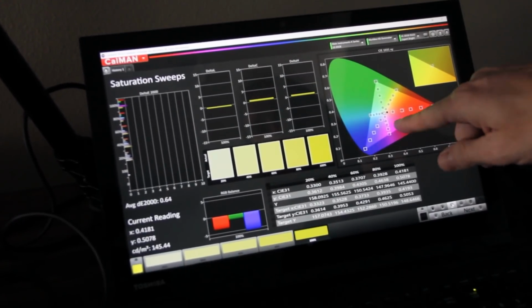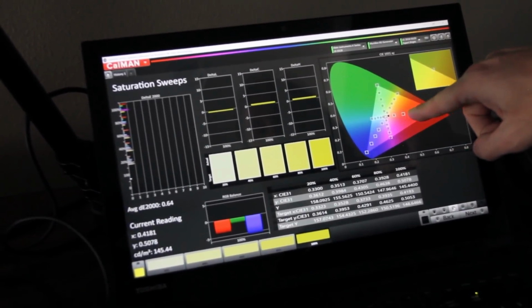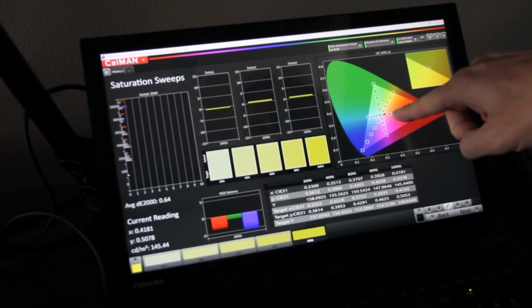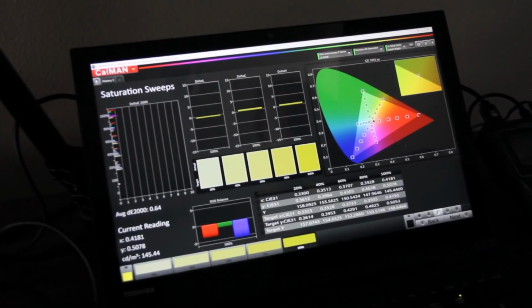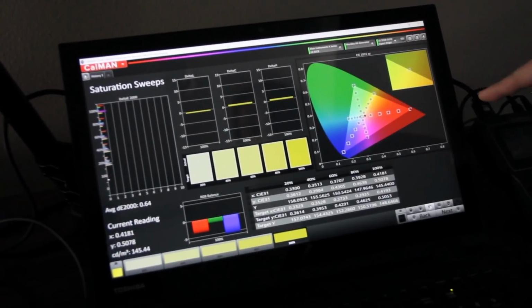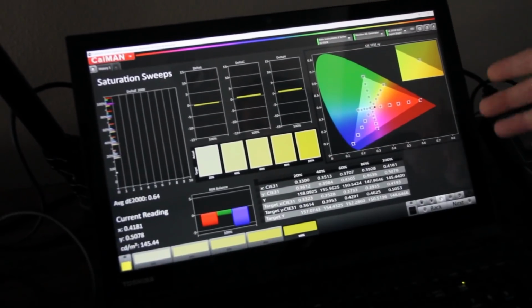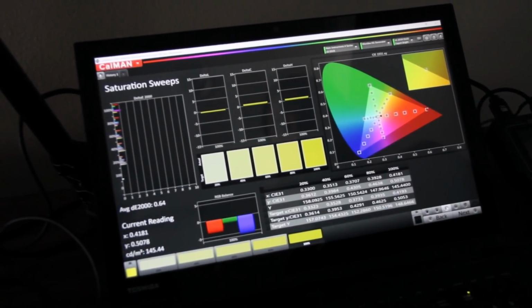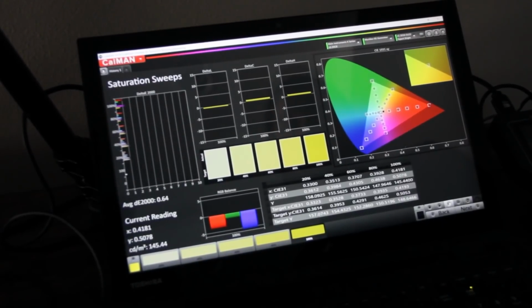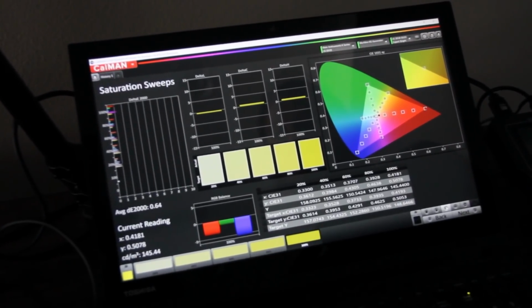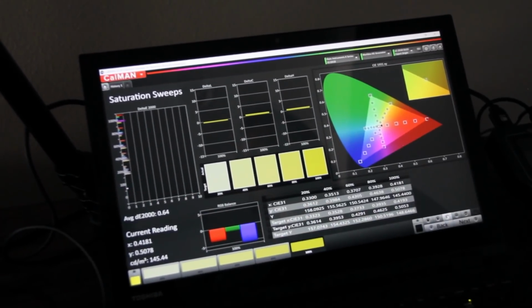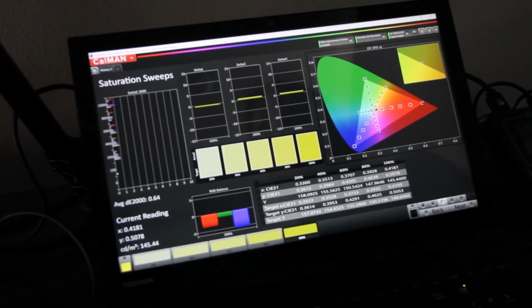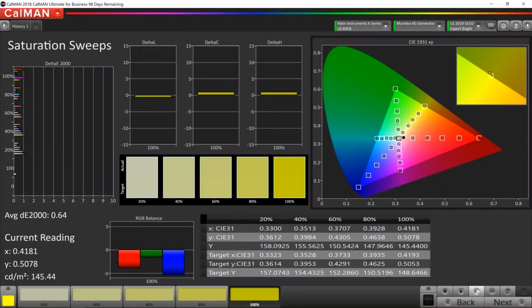So in other words, the middle dot here is white, and as you work your way out towards the edge of the triangle, you go from like a light pink to a middle red to a heavier red, and then eventually to red. So now we're tracking the performance and the accuracy of the in-between shades of red from white all the way out to perfect red, or 100% saturated red rather. And what you'll notice here when you look at the saturation sweeps test, the average delta error was a 0.6 for all of the measurements it took, which is awesome. Again, that's below 1. That's incredibly accurate. And you take a look at the CIE chart and take a look at the targets versus the little dots where the measurements were taken. Everything's pretty close to being perfect.